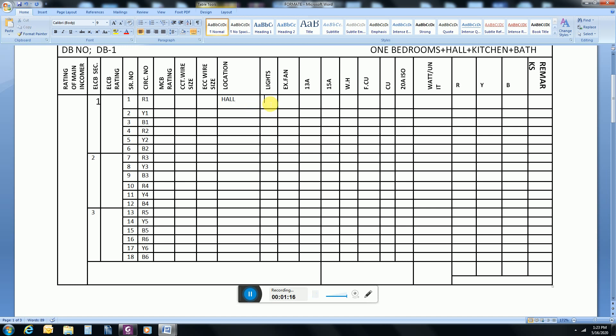Starting from hall: there are five lights in the hall, and the MCB rating for these lights will be 10 ampere. Circuit wire size will be 2.5mm and ECC wire size will be 2.5mm. Each light is 100 watt, so the total load on our phase will be 500 watts. Similarly, the next circuit will also be 10 ampere, wire 2.5mm.